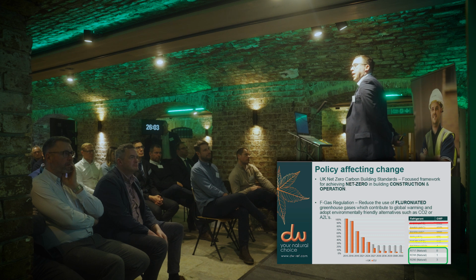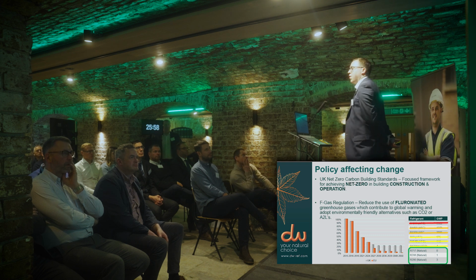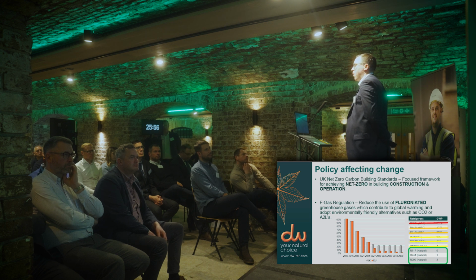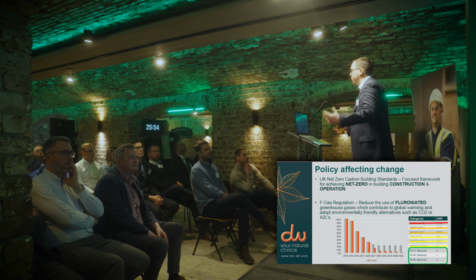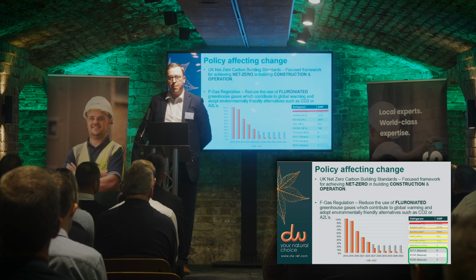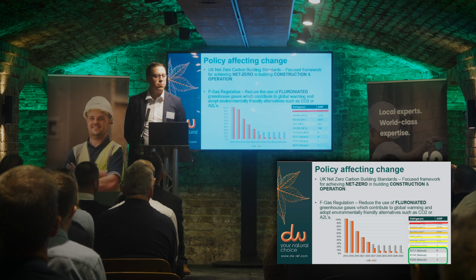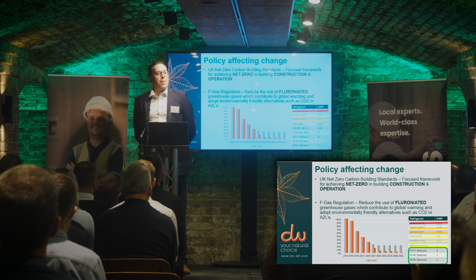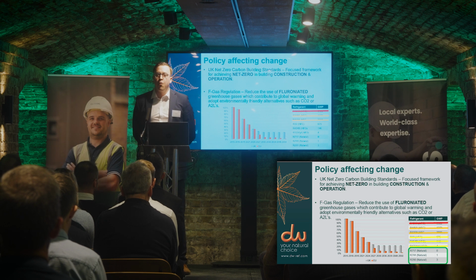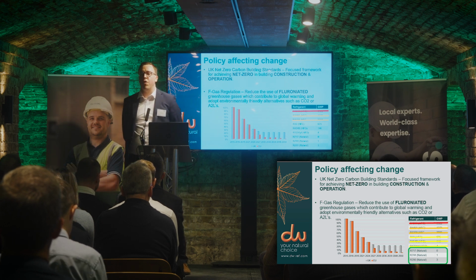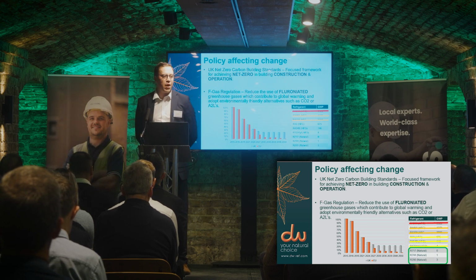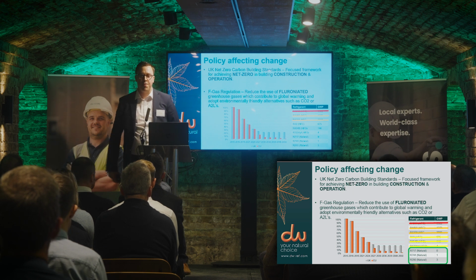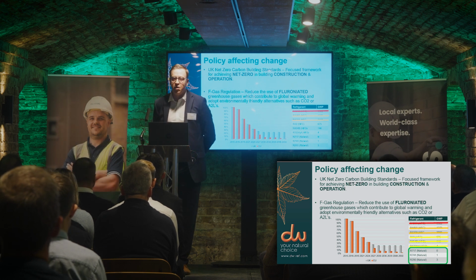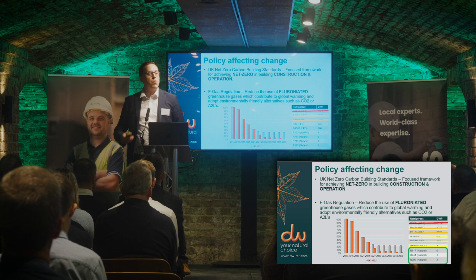So there are 2 strands: reducing the amount of refrigerant that can be sold on the market, and outright bans. 404A, which was a common refrigerant everybody's probably heard of, is now banned, and you can't put that in new systems moving forward. A replacement for 404 was 448A, and actually now we'd advise not to put new systems in on 448A, 449, or 410, which is a very common refrigerant in air conditioning and heat pumps.